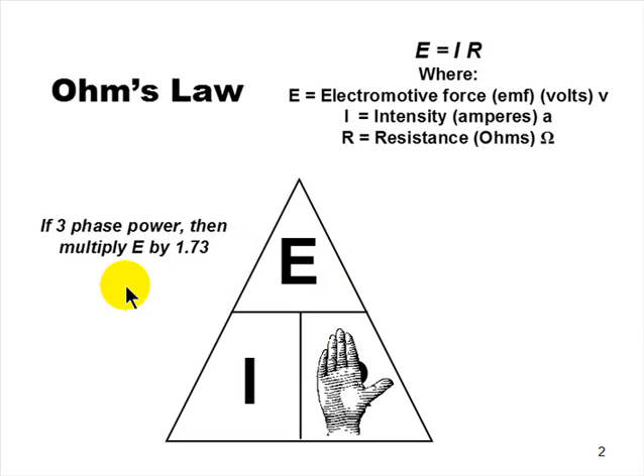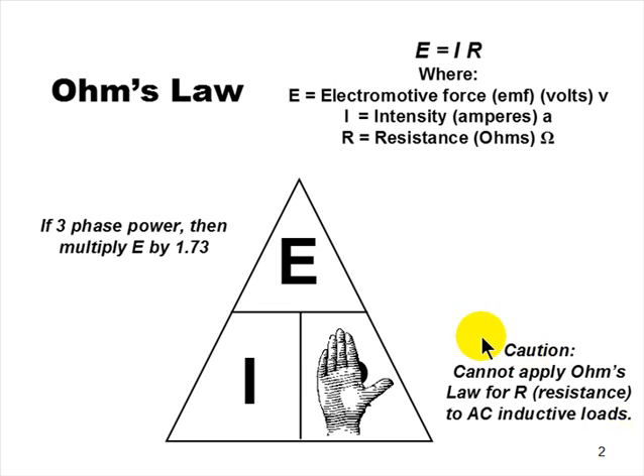All right? Now, just some things about this. And this is not on the exam, but I can't talk about Ohm's Law without telling you this. Ohm's Law does apply to three-phase circuits, but you have to multiply your voltage by 1.73. 1.73 is the square root of 3. So your voltage in a 240-volt three-phase circuit is not 240 volts for this calculation. It's 240 plus 73%. Also, for your own reference, you can't solve for resistance on inductive loads using Ohm's Law. Ohm's Law only works for strictly resistive loads because there were no inductive loads when this was developed, back in Sir George Ohm's day. You cannot apply Ohm's Law for resistance to AC inductive loads.